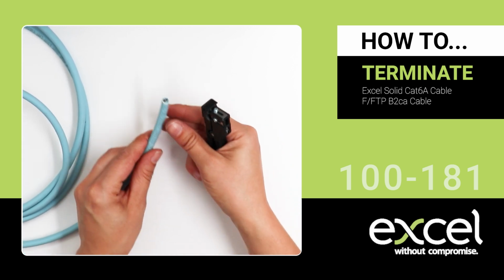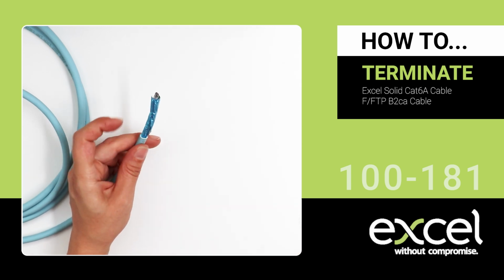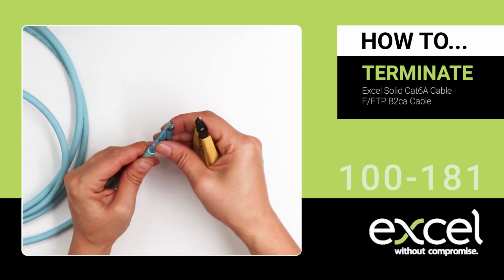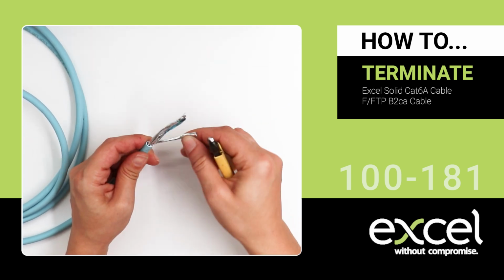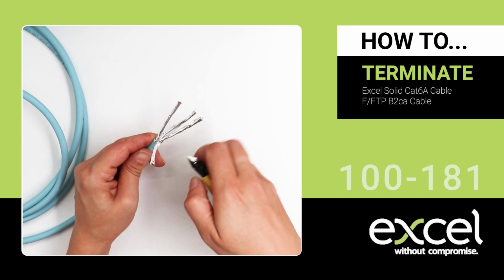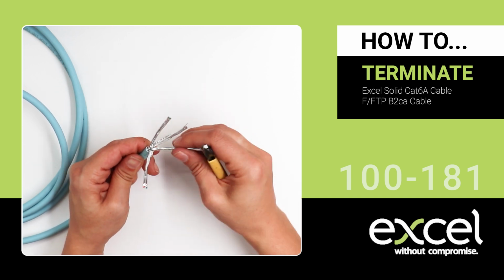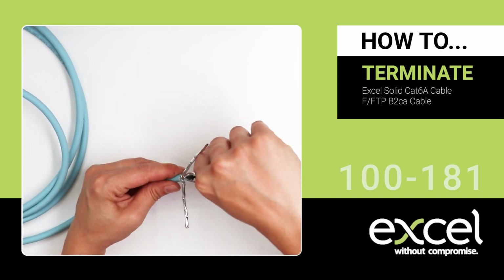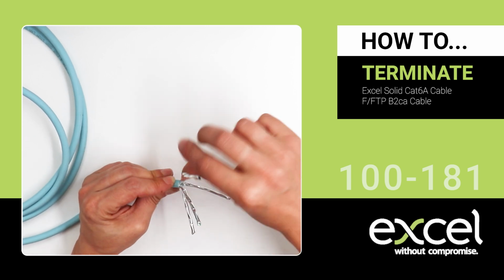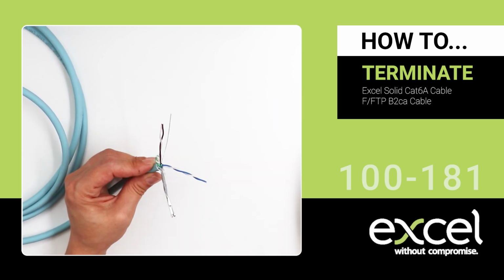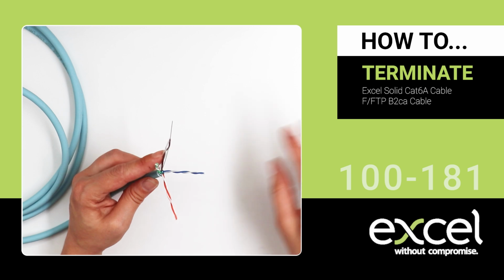Score the sheath, bend the cable to break it, and remove the jacket. Snip and remove the outer foil layer using the side cutters. Then snip the foil from the pairs with the side cutters. Be careful not to cut the drain wire. Unwrap the foil and remove from the individual pairs of cable.